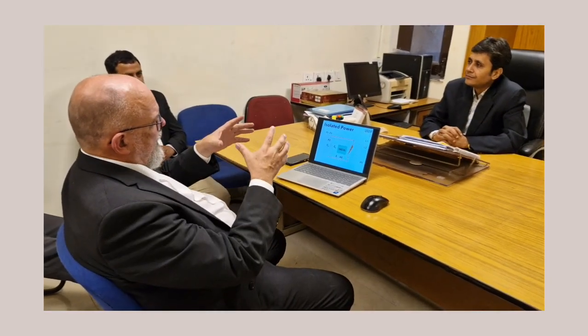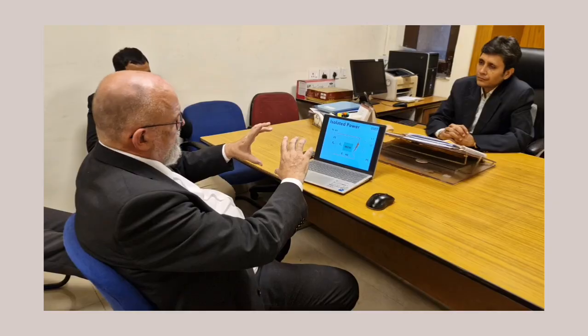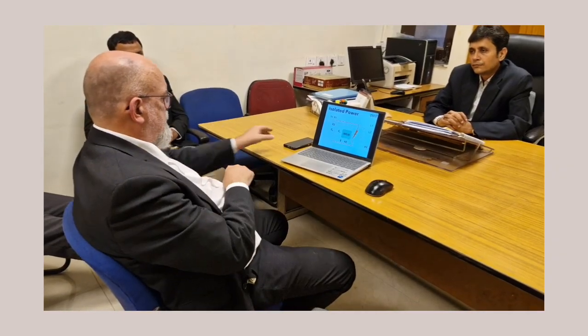Exactly, and in this way, when we have the remote alarm unit in our operating theater, in the ICU, we have a second one connected with Modbus in the technical room where the maintenance people are sitting. Or we can have a signal coming through the mobile phone with an SMS or a phone call escalated by the IMD. So the maintenance people directly get information: go to ICU number 5, bed number 3 has a problem. The IMD only tells you that there is a fault in the critical room.